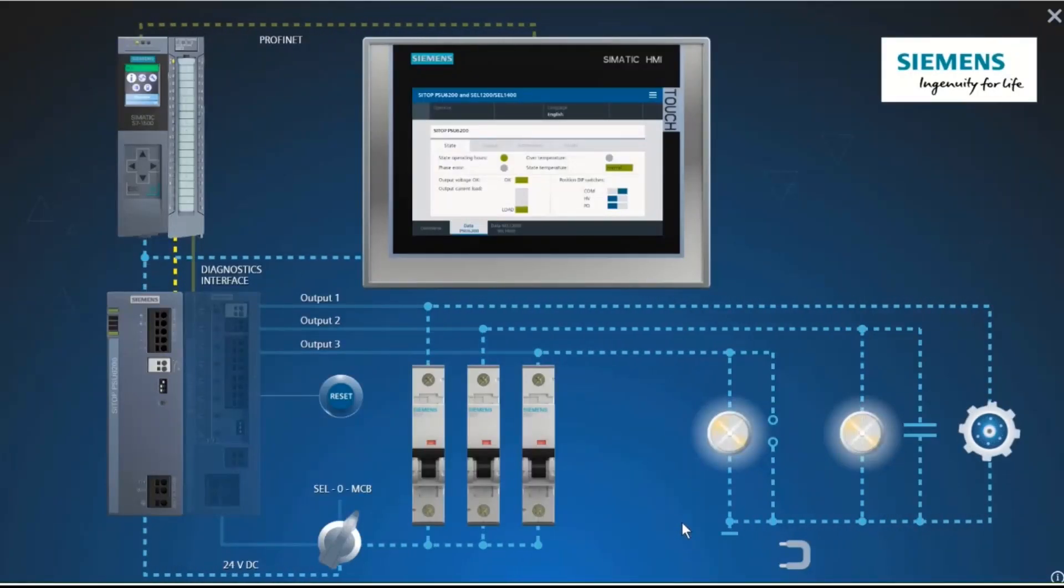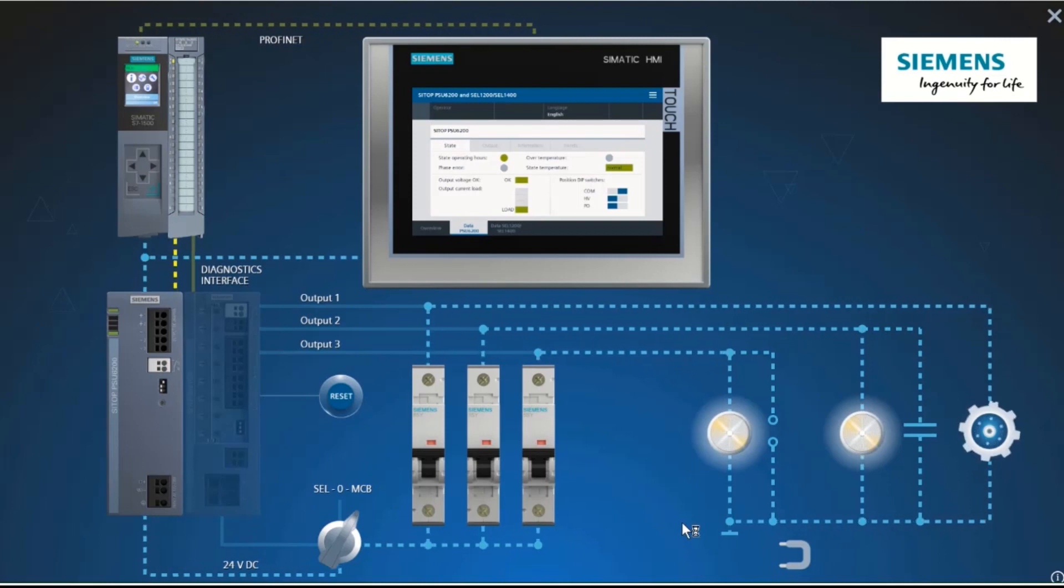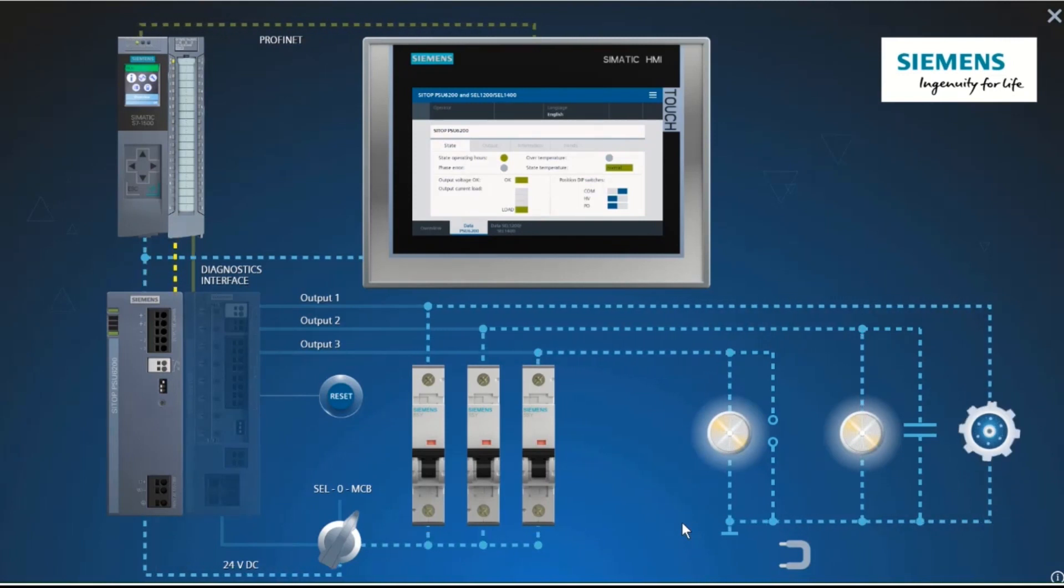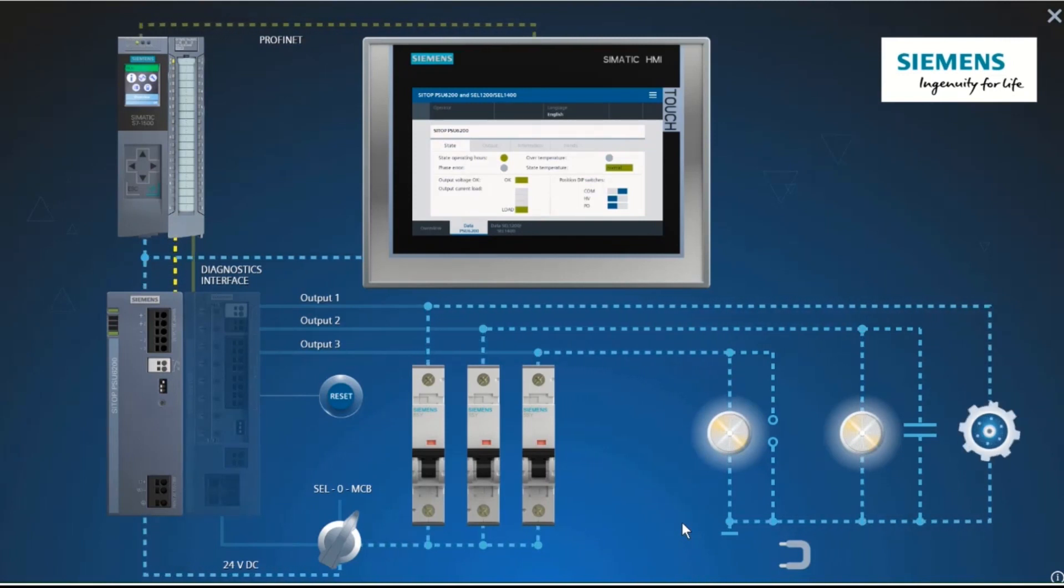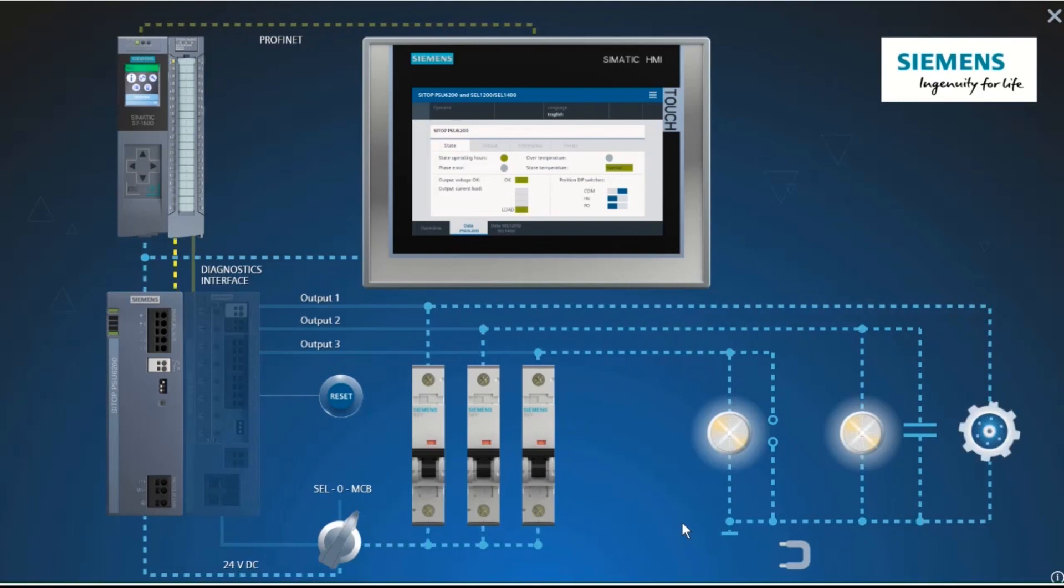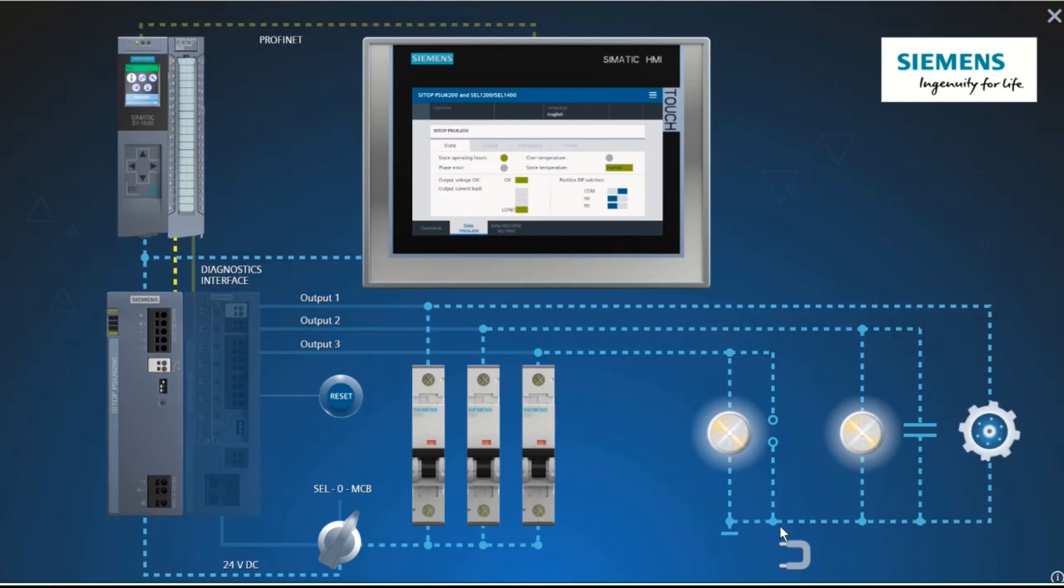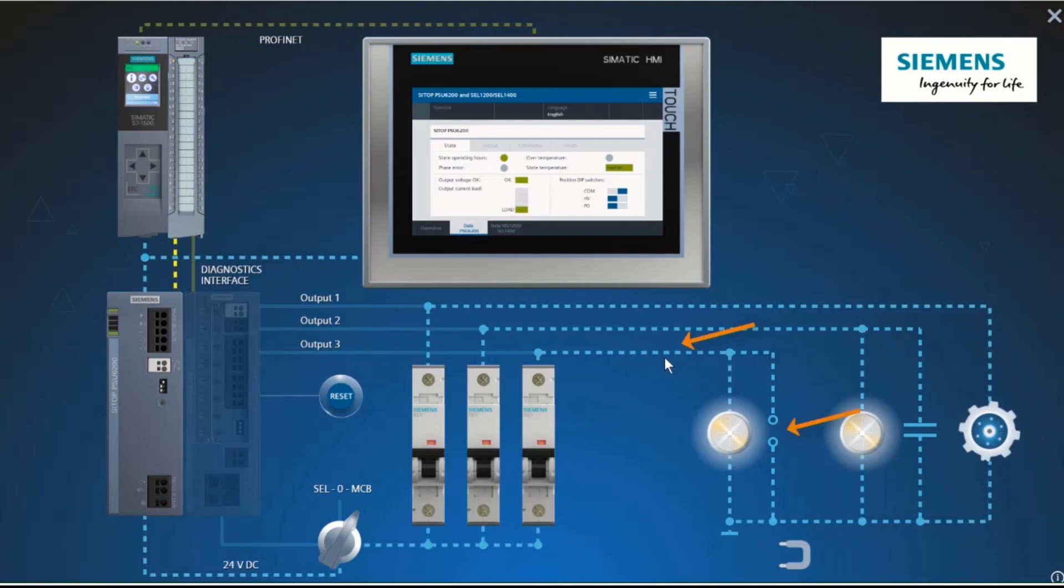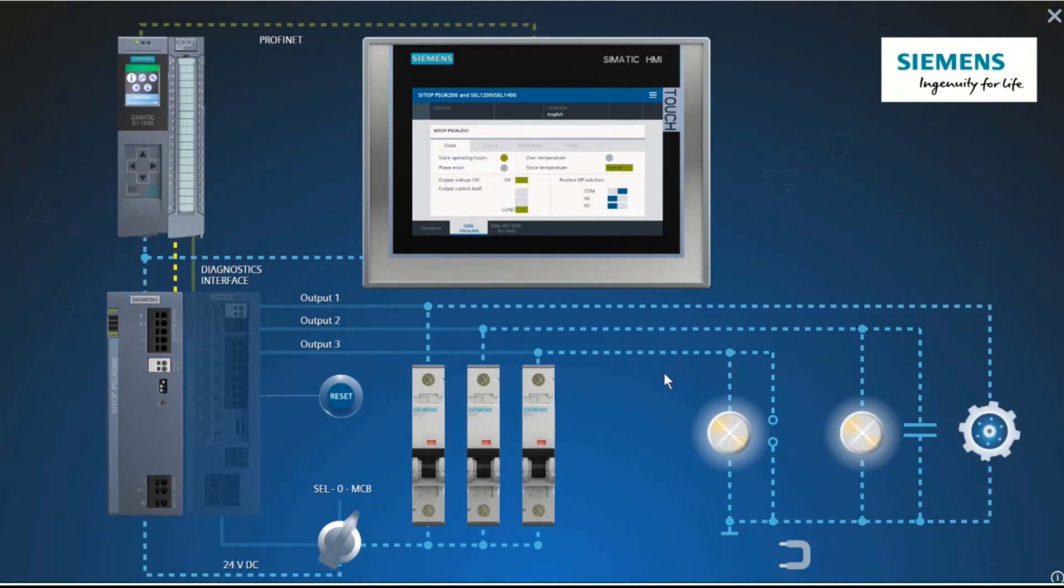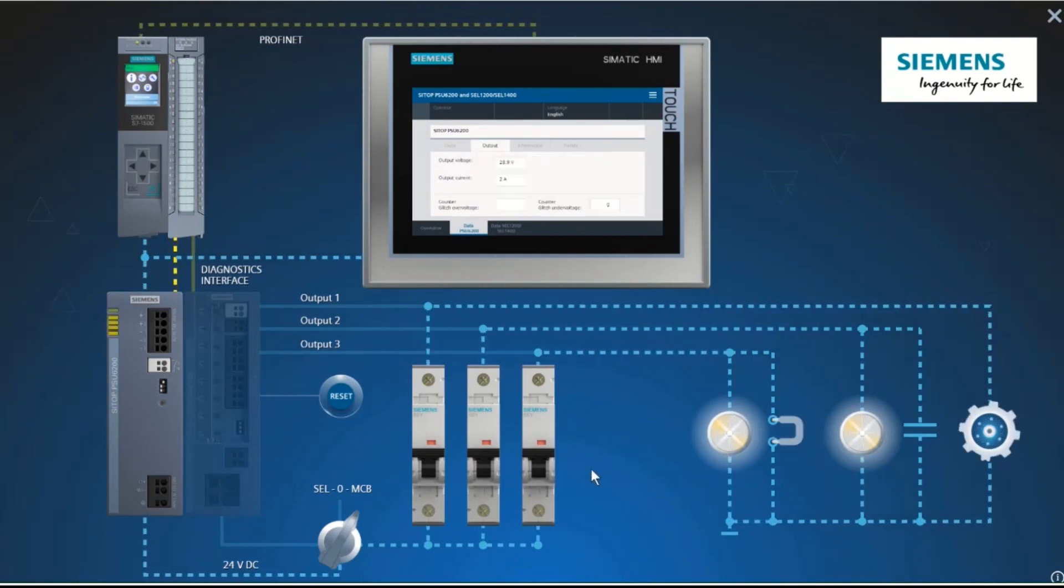Now we simulate a short circuit downstream of a circuit breaker. To be precise, a short circuit as it usually occurs in practice. This is not a full short circuit, but a short circuit with contact and line resistances. The third branch is short-circuited by this shorting link.